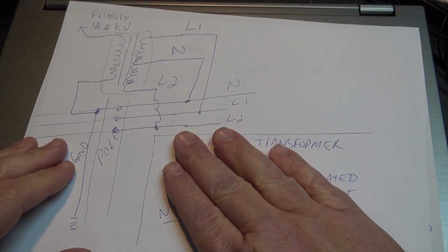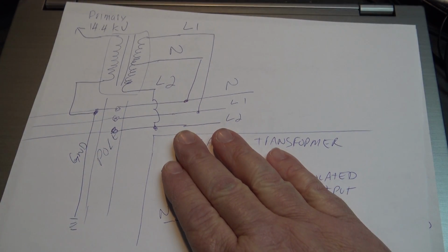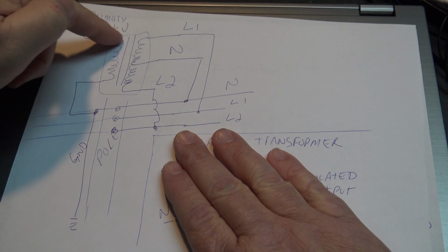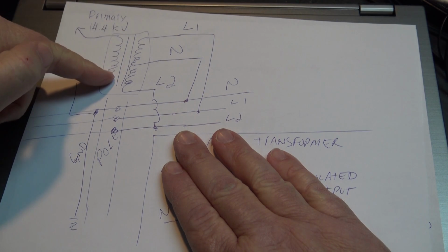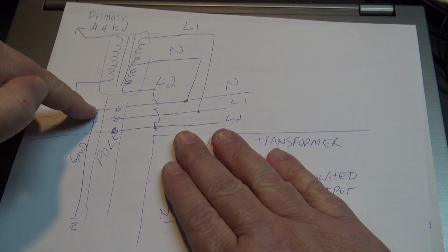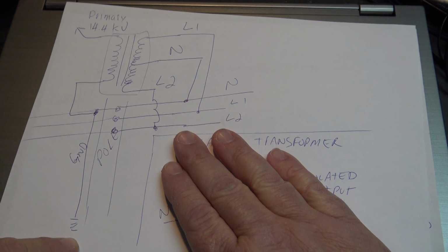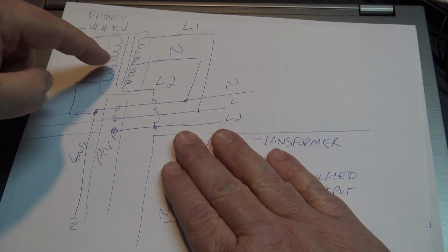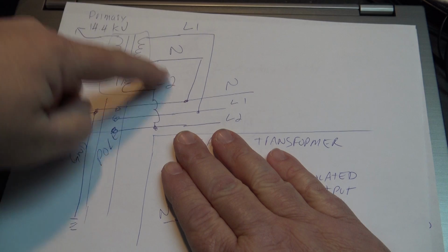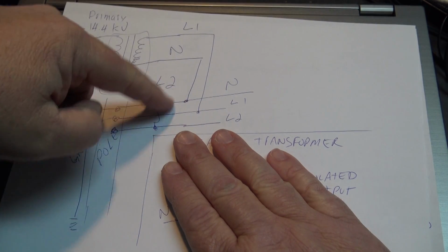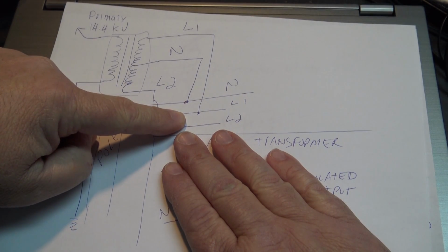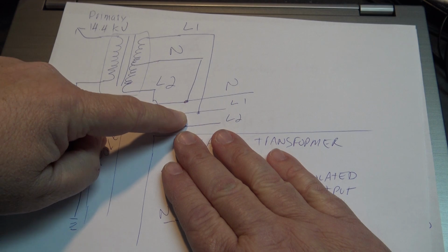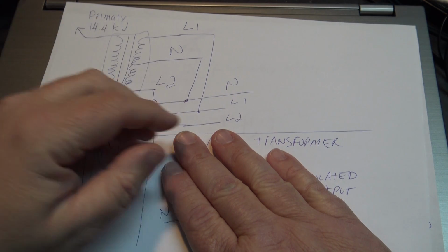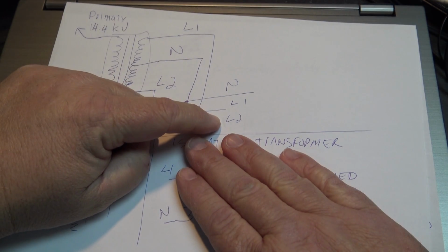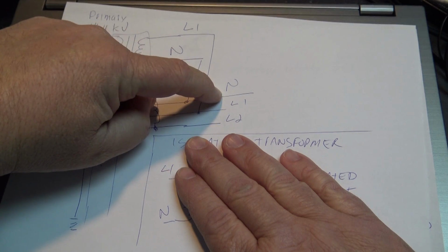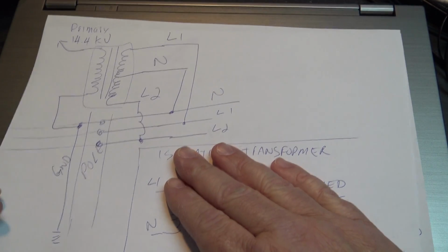So this more represents a schematic diagram. Here's your pole. Your primary 14 kilovolts is coming into the primary side. The other side of that winding is tied to the neutral line, which, of course, is tied to ground. And then you've got your center tap, which is tied to neutral, line one and line two, to your 120-volt split that feeds your house. So between line one and line two, you have 240 volts. Between line one and neutral, or line two and neutral, you'd have 120.